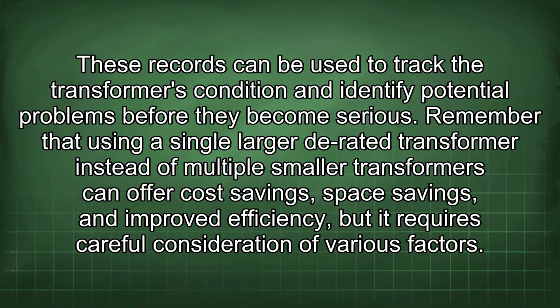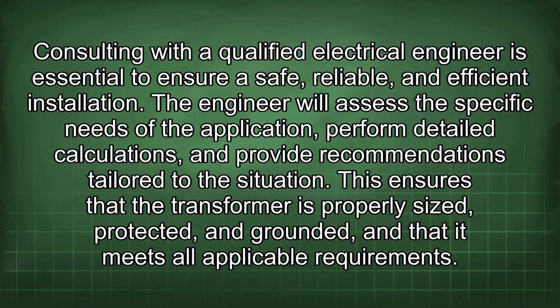These records can be used to track the transformer's condition and identify potential problems before they become serious. Remember that using a single larger derated transformer instead of multiple smaller transformers can offer cost savings, space savings, and improved efficiency, but it requires careful consideration of various factors. Consulting with a qualified electrical engineer is essential to ensure a safe, reliable, and efficient installation. The engineer will assess the specific needs of the application, perform detailed calculations, and provide recommendations tailored to the situation. This ensures that the transformer is properly sized, protected, and grounded, and that it meets all applicable requirements.